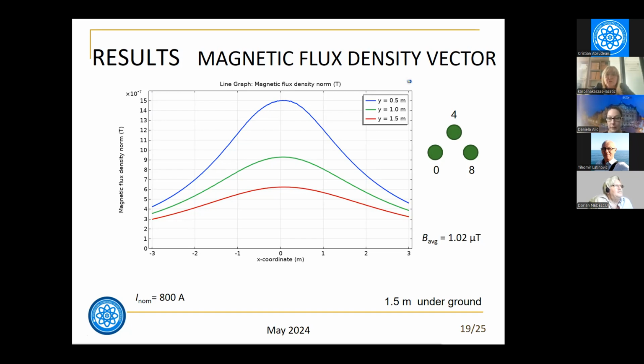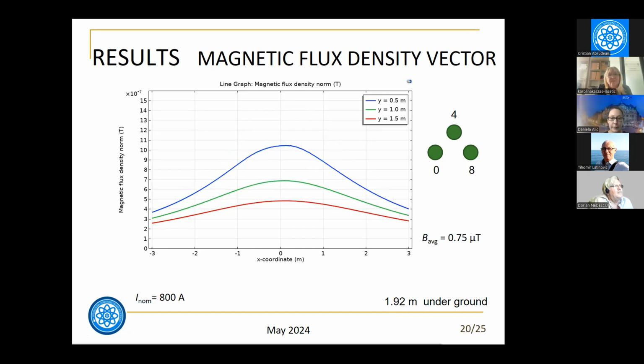These values are for the cables where the phases are 1.5 meter underground. I forgot to mention that all the calculations were made with the current of 800 amps as a nominal value for this system. When there are different heights, it depends on the terrain where the cables are buried.